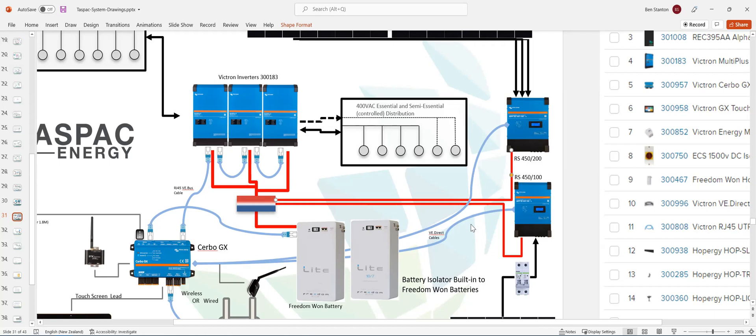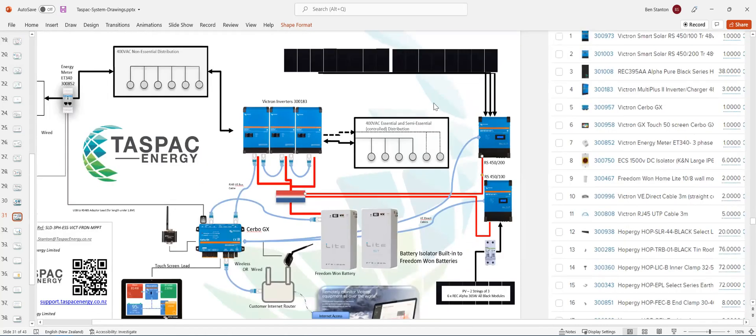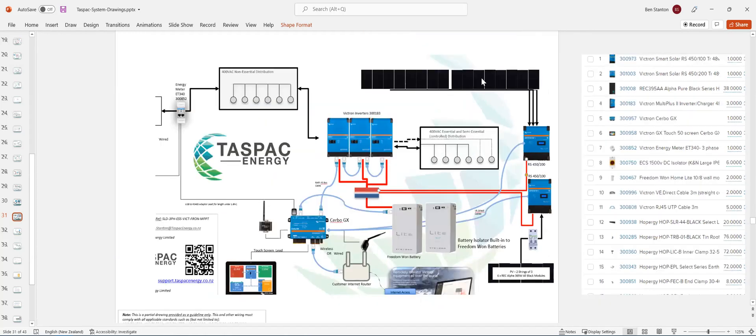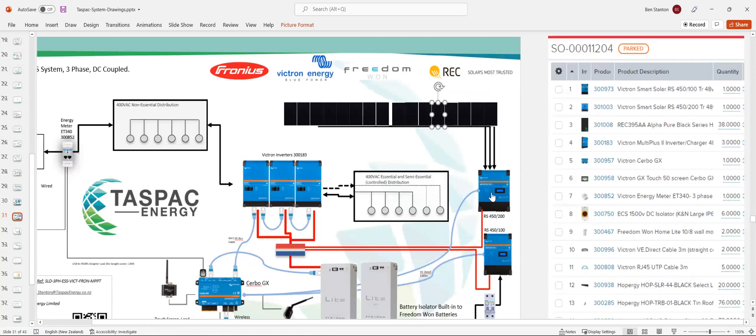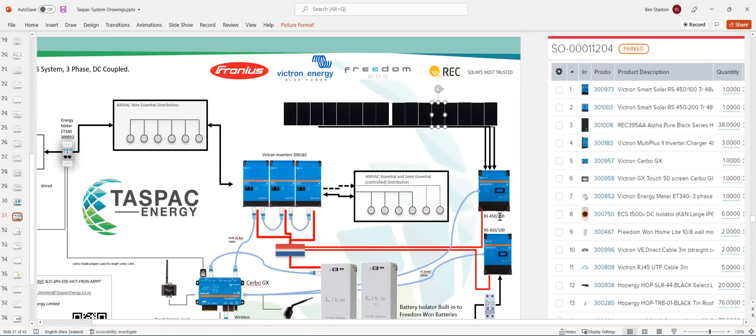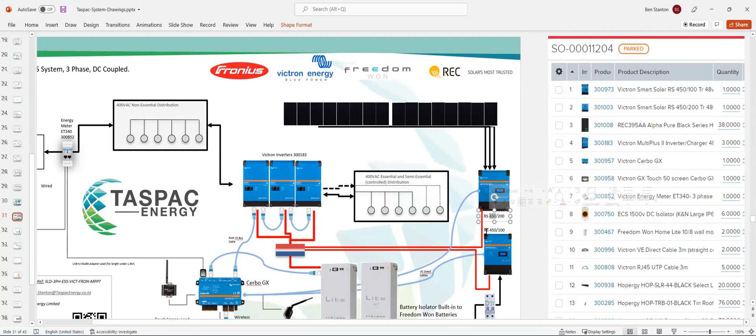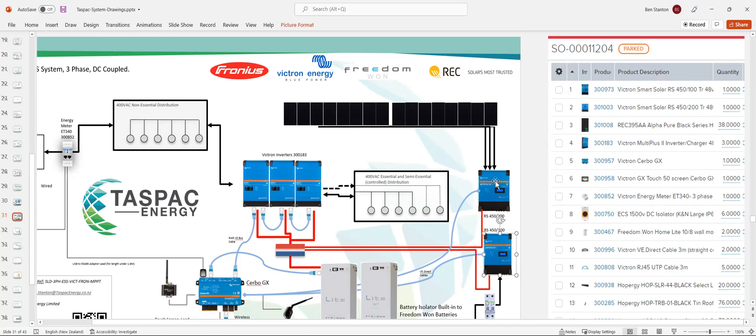Now, what you're going to do is you're then going to connect your DC panels, solar panels, to the RS inverters. Now, the RS200 has four MPPT trackers, and each MPPT can handle up to 450 volts. Same with the RS100, except the 100 only has two trackers. So the 200 has four trackers, the 100 has two trackers. So you can do two strings. You can also parallel strings if you want to, but usually it's not required.